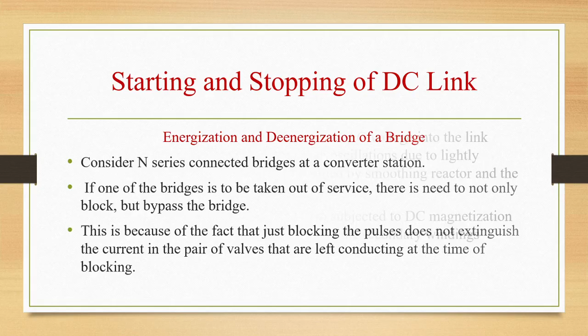Okay. So let us see what exactly we have seen in the starting and stopping of a DC link. There we have seen the energization and de-energization of a bridge. So we have considered N series connected bridges at a converter station. If one of the bridges is to be taken out of service, there is need to not only block but bypass the bridge. This is because just blocking the pulses will not extinguish the current in the pair of valves that are left conducting at the time of blocking. The continued conduction of this pair injects AC voltage into the link, which can give rise to current and voltage oscillations due to lightly damped oscillatory circuit in the link formed by smoothing reactor and the line capacitance.